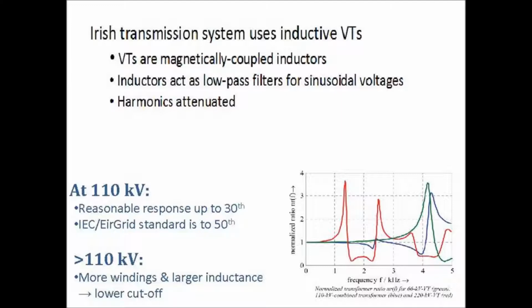The green plot shows the 66 kV VT, and you can see that it's quite flat all the way out past 2 kHz and close enough to 3 kHz. So that covers all the way up to beyond the 50th harmonic. The blue one, on the other hand, is the 110 kV, and it's okay up as far as, I suppose, where things start to change, just around 1.5 kHz or thereabouts. Generally, beyond that point you're not quite as sure about the reliability of your VT, and you can't say the harmonics are perfectly recorded.